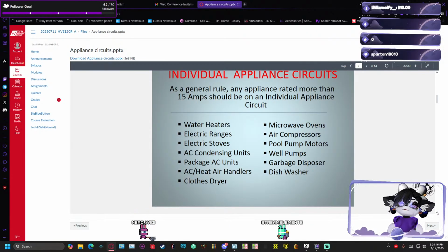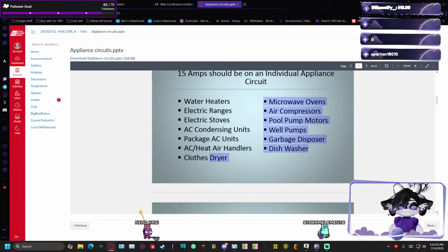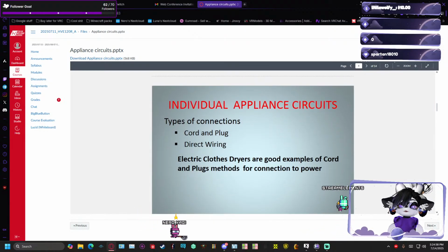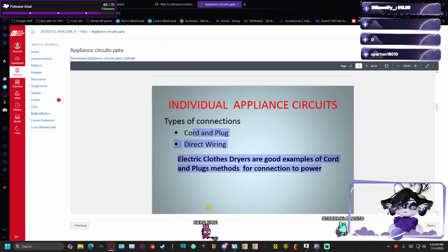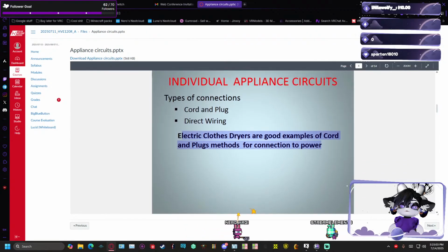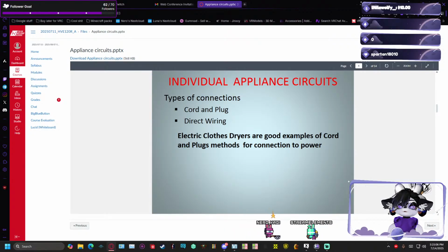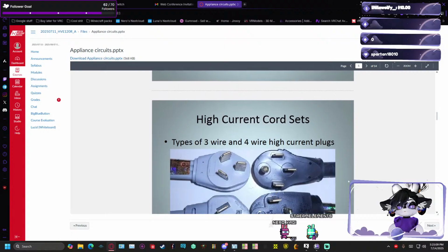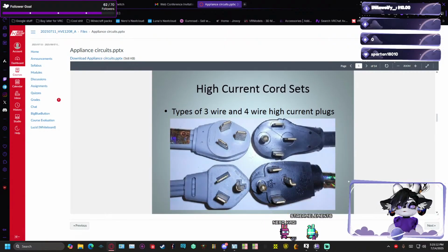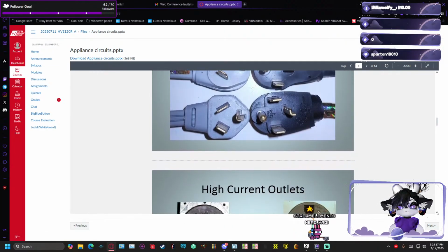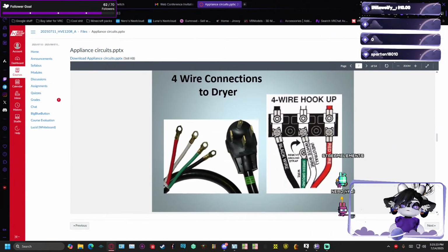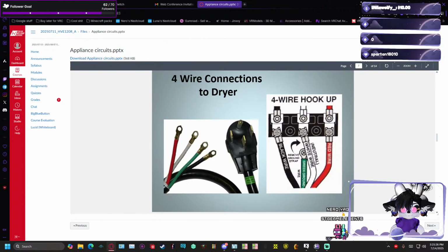Any appliance rated more than 15 amps should be on an individual appliance circuit. Individual appliance circuits: cord and plug, direct wiring. Electric clothes dryers are a good example of cord and plug methods for connection to power. High current cord sets, types of three-wire and four-wire high current plugs. You've seen these before. High current outlets look like such. A four-wire connection to a dryer.